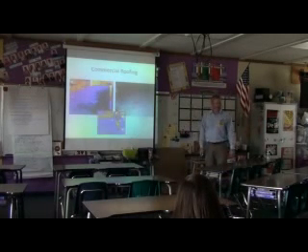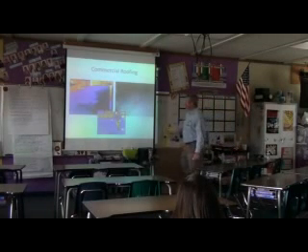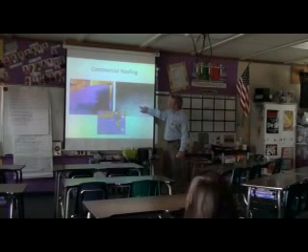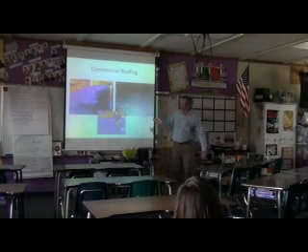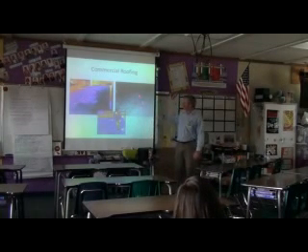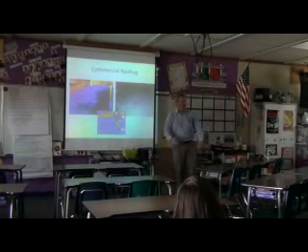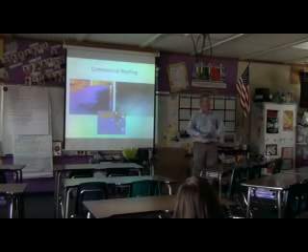This is a university down in San Diego. I can see water in the roofs. Okay? So when we look at a roof, this roof looks the same. I made all these marks because this is all trapped water that's inside the roof, and then we mark it off, and they just have to replace what's wet. Instead, some people replace the whole roof.